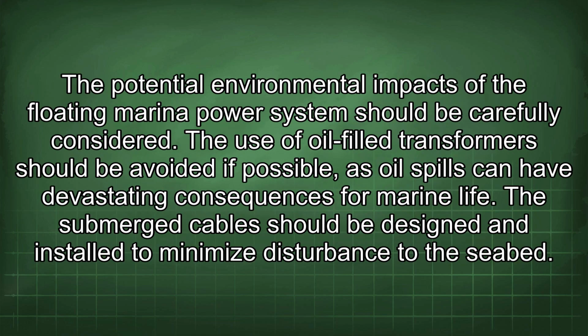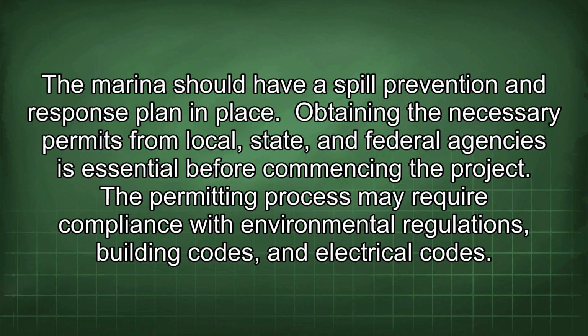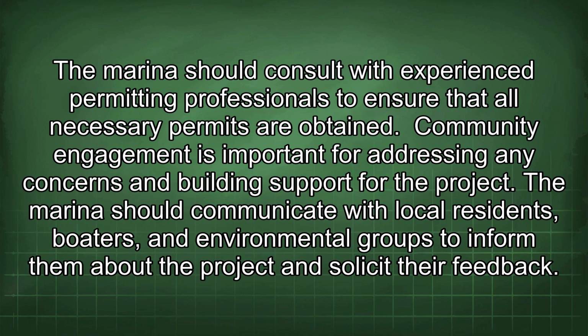The potential environmental impacts of the floating marina power system should be carefully considered. The use of oil-filled transformers should be avoided if possible, as oil spills can have devastating consequences for marine life. The submerged cable should be designed and installed to minimize disturbance to the seabed. The marina should have a spill prevention and response plan in place. Obtaining the necessary permits from local, state, and federal agencies is essential before commencing the project. The permitting process may require compliance with environmental regulations, building codes, and electrical codes. The marina should consult with experienced permitting professionals to ensure that all necessary permits are obtained.